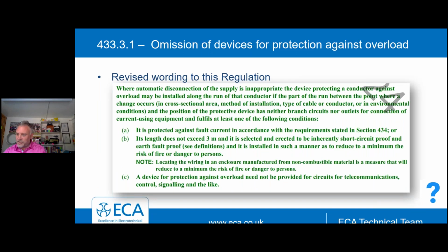It's quite a big change. Regulation 433.3.1, so omission of devices for protection against overload, has been revised. However, the ECA believe there's an error in the redrafting. We think some of the wording from 433.3.1 and 433.2.2 have been interchanged, so we're not quite sure that this has been drafted correctly.